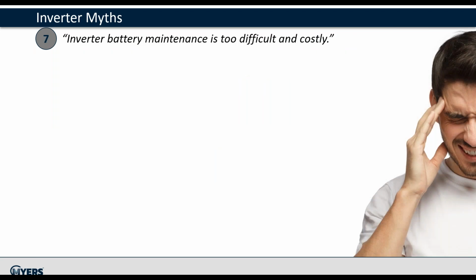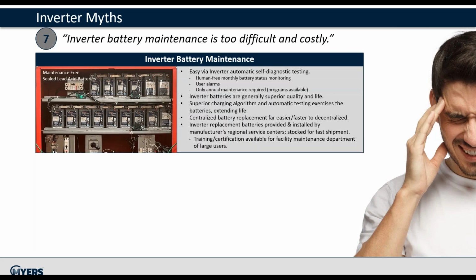The next myth is inverter battery maintenance is too difficult and costly. Inverters perform routine monthly and annual self-tests that are governed by NFPA 101 and can interface to fire alarm panels, BMS systems, or other monitoring systems. The batteries used in central systems are superior quality to other emergency systems. The charging algorithm, minimal ripple current in the battery string, and the automatic testing exercise the battery, extending its life. The battery's maintenance and replacement for central lighting inverters is much easier than other technologies.